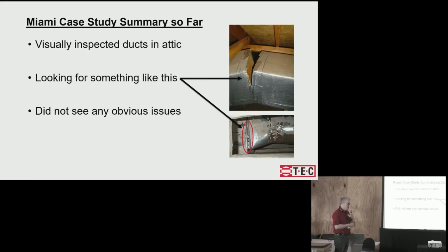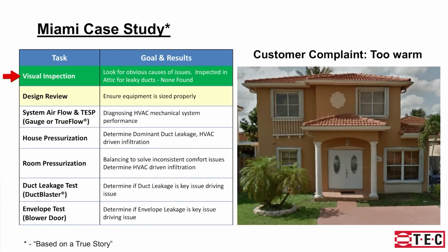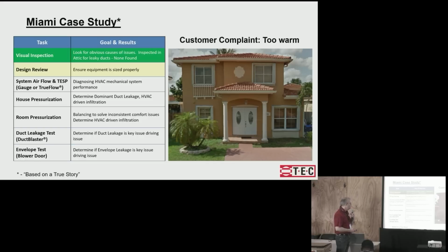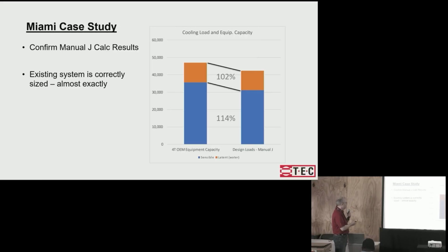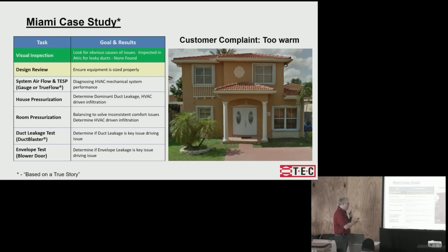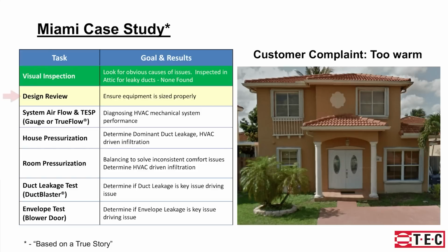Okay, in this house, the technician did go in the attic and didn't see any obvious duct leaks. So we checked that off and say, okay, well, we did that. Visual inspection did not reveal any major duct leaks. Next thing you want to do is be checking the airflow. If you've got a system that's way low on airflow, that means you're way low on capacity too. So in this case, the technician did check the airflow with the MeasureQuick and with the TrueFlow grid and verify that the airflow was okay. It's within the range that's acceptable. It's not a reason that you'd be slipping 8 degrees on a day that's not even a design day. Look at the design review.